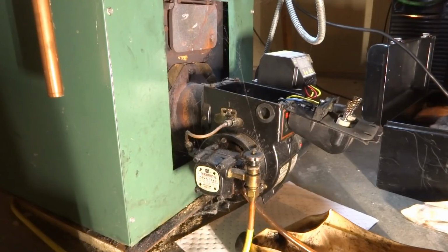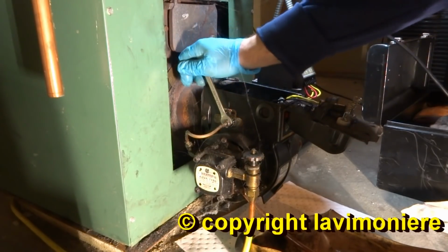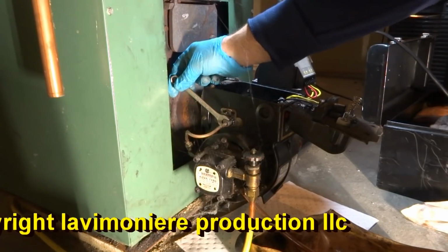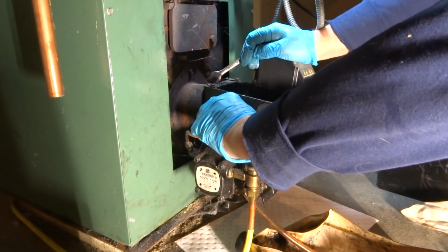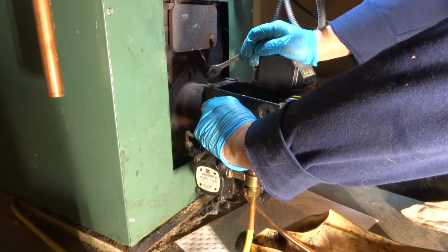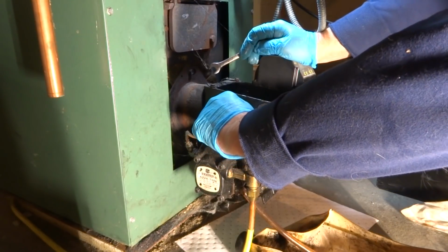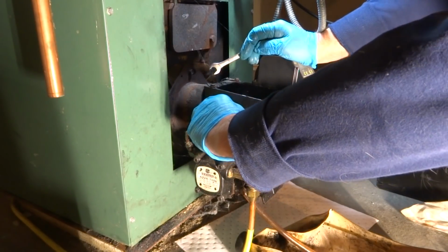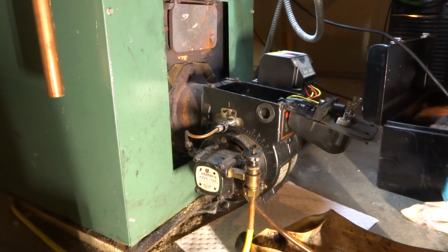Now, has this one been tripping too? No, just that the one's working fine. Just the furnace. At first look, I think it might be that transformer that's acting up. That would be my first impression, that electronic transformer, see that's a constant duty control. The old ones weren't designed to work constant duty. They were designed to drop out, like this control right here will drop the transformer out so it doesn't spark continuously. And those electronic ones, they'll be known to work sometimes, they won't. So sometimes you hit the button and it would start, and other times it wouldn't.